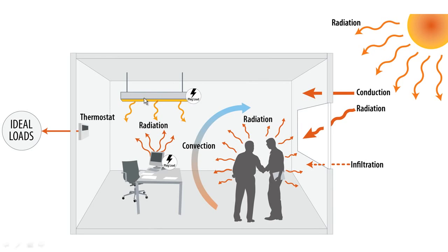Of course, we have lights we add to light up the space, but they also introduce heat to the space. So we have two kinds of loads with that: the heat being added to the space, and also a plug load, which is just an electrical load being used to create that heat. So you have a double whammy if you're trying to cool your zone. Then we have something like a computer here, which acts very much like a light. From EnergyPlus's standpoint, with a few exceptions, it's not about the light it's creating, it's about the electricity it's using and the heat that it's generating.